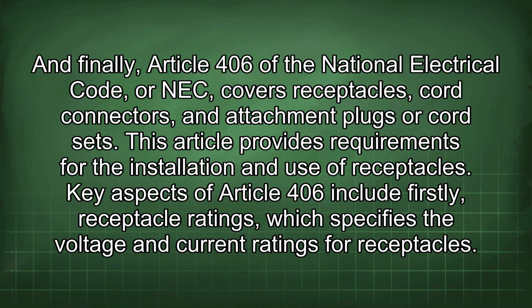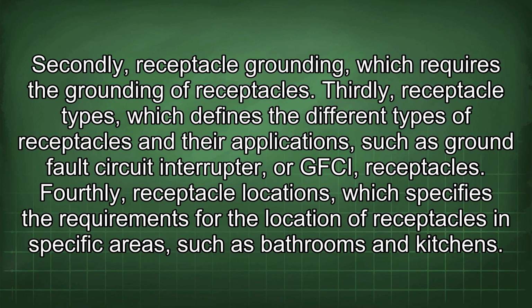And finally, Article 406 of the National Electrical Code, or NEC, covers receptacles, cord connectors, and attachment plugs or cord sets. This article provides requirements for the installation and use of receptacles. Key aspects of Article 406 include, firstly, receptacle ratings, which specifies the voltage and current ratings for receptacles. Secondly, receptacle grounding, which requires the grounding of receptacles. Thirdly, receptacle types, which defines the different types of receptacles and their applications, such as ground fault circuit interrupter, or GFCI, receptacles. Fourthly, receptacle locations, which specifies the requirements for the location of receptacles in specific areas, such as bathrooms and kitchens.